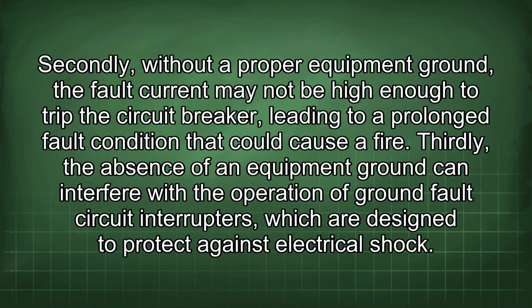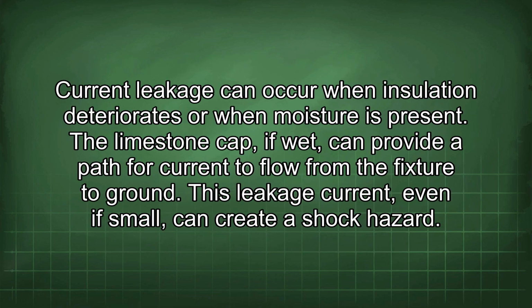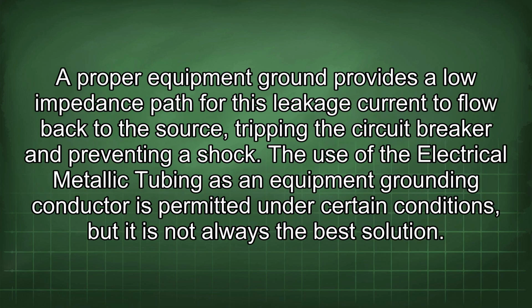Thirdly, the absence of an equipment ground can interfere with the operation of ground fault circuit interrupters, which are designed to protect against electrical shock. Current leakage can occur when insulation deteriorates or when moisture is present. The limestone cap, if wet, can provide a path for current to flow from the fixture to ground. This leakage current, even if small, can create a shock hazard. A proper equipment ground provides a low impedance path for this leakage current to flow back to the source, tripping the circuit breaker and preventing a shock.